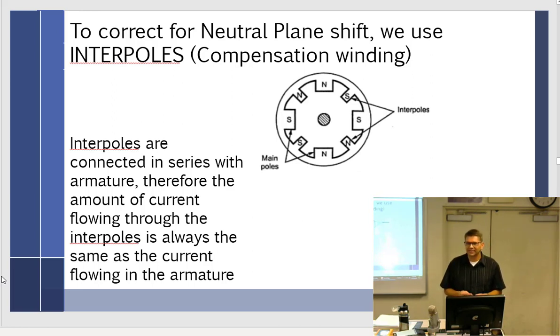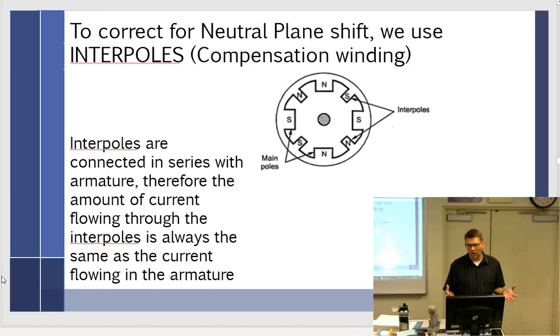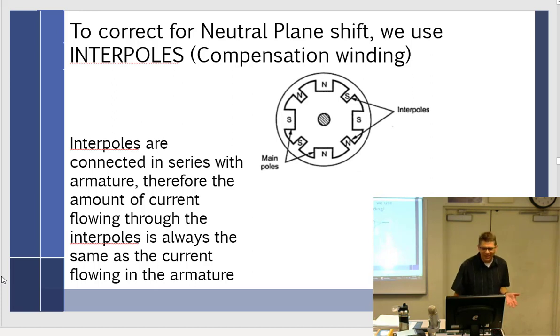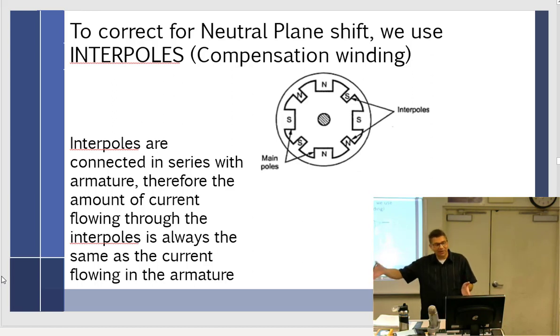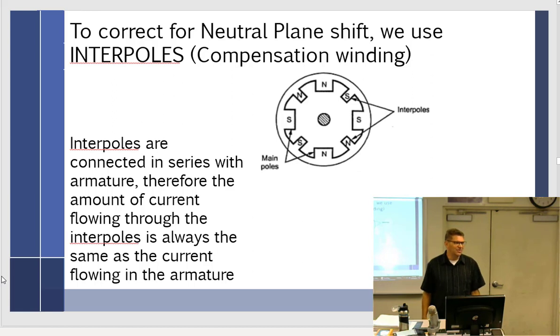Interpoles are these little tiny poles in between the main poles, also called compensation windings. The interpole is going to correct for the amount of current flowing through the armature, but somehow we have to tell the interpoles how much current is flowing. The more current that flows through the armature, the stronger the interpoles have to be to compensate. So we put them in series with the armature — that way any current flowing through the armature also flows through the interpoles.